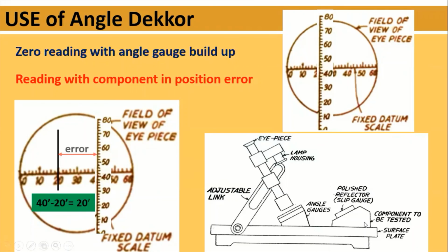So in this way we can read the instrument, or you can make use of the angle Dekkor to a very high accuracy. Up to 1 minute is possible to measure in the angle Dekkor.